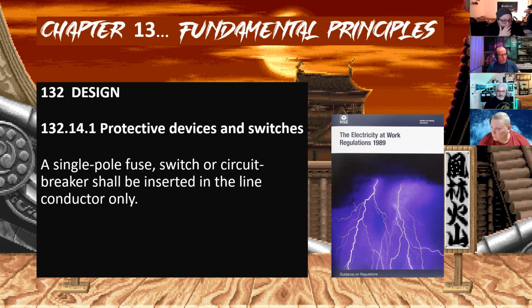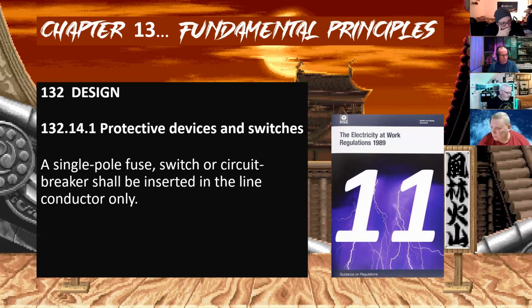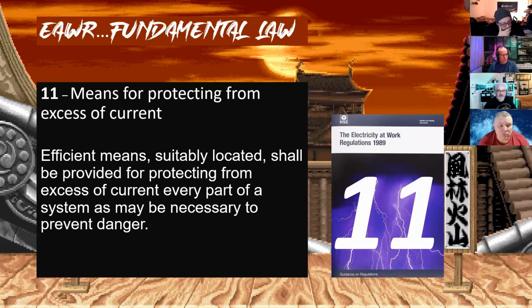So what do we think, everyone? I'm not going to poll this one - I think I'd use number 11, means for protecting from excess of current. John, yeah, I think that's fine. Efficient means suitably located shall be provided for protecting from excessive current every part of a system as may be necessary to prevent danger. So if you put the switching device in the neutral, it's not going to prevent danger, because the thing will still be live and potentially dangerous for someone who didn't expect that.